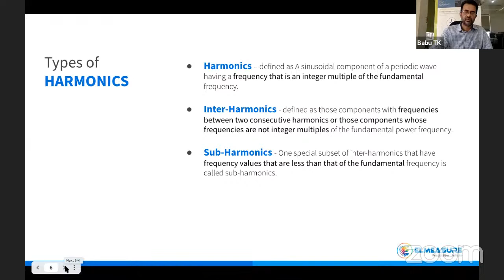Sources of interharmonics: today, if you look at UPS, you convert AC to DC, and then convert that back again to AC. Most of them are of the same frequency, so not much of a problem. Yes, it does create interharmonics, but as long as the frequency is matching, it is not that bad. But there are situations where I would generate a 50 hertz from a 50 hertz source, make DC and then make maybe a 64 hertz waveform or different frequencies. Such things can cause interharmonics quite badly.